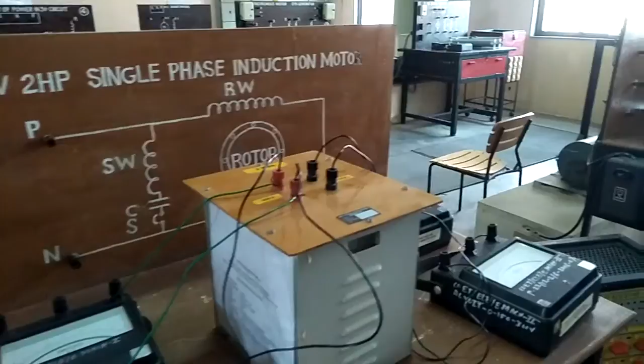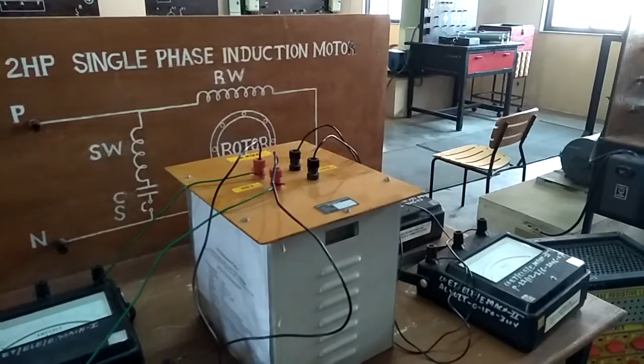For the polarity test, we will again switch off the supply, and because we have to connect a voltmeter in a different way, we will disconnect the load terminal. What we will do is connect a link between the two terminals, one of the primary winding and one of the secondary winding.